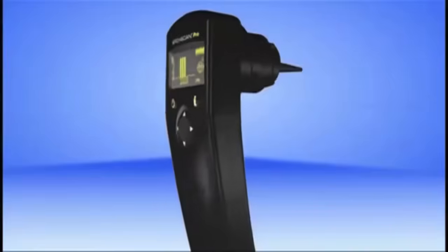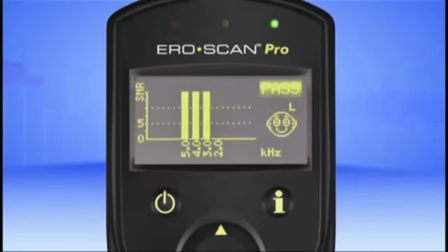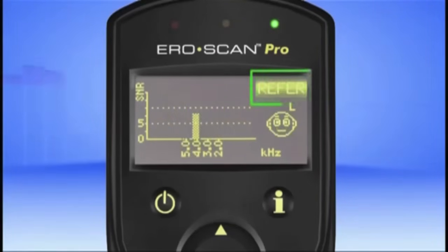The results of the test are instantly and automatically saved in flash memory once the test has been completed. They'll be saved even if the unit is turned off or the Ero Scan Pro's internal batteries are removed. They'll be displayed on the device's screen and show the following information: the ear tested, a graph of the results, frequencies tested, and whether the test was a pass or refer.